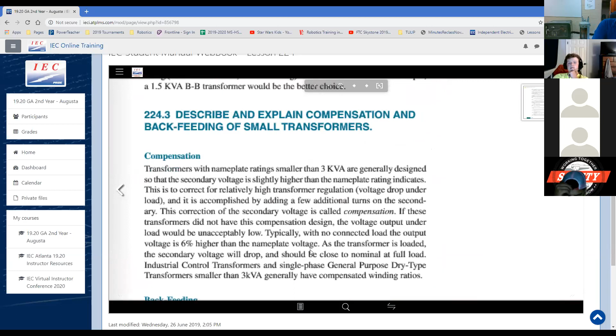And there's a lot of other precautions you have to be careful for, because it says it right here. The inrush current is the problem. That's like when these backfeed up a line, that inrush is what explodes transformers down the line. So you have to be careful of that. And of course, it's going to open up every overcurrent protection device in America. So you want to comply with the NEC and avoid nuisance opening. On the primary side of the transformer, when energized, make sure you coordinate it, and you got a centralized overcurrent protection device for that.